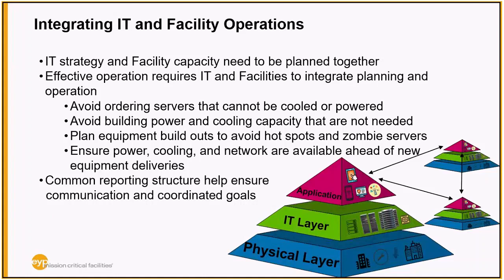Another client, after moving from a siloed approach to a more integrated one, was surprised to learn that incremental improvements in availability from adding physical infrastructure actually meant higher availability at lower cost — by building an additional data center with both sites at slightly lower redundancy and providing redundancy at the application level, so a problem at one site could seamlessly fail over to another. The closer the two silos come together in the management chain, the better they are coordinated.